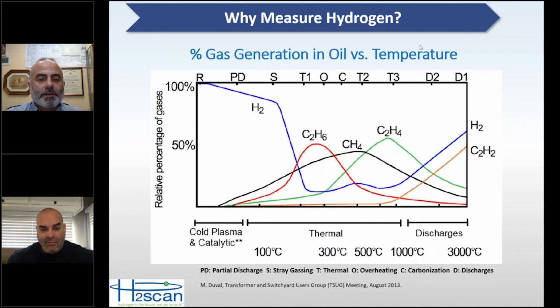And so this is an interesting graph that I came across at a conference a few years ago, and it really helped me make sense out of the different gases, when people would show me their DGA reports, of what was really going on. And if you look on a percentage basis at lower temperatures, and this is a relative thing, around 100, 150 degrees C, generally the primary gas you're going to see is hydrogen. And as the temperature increases, that's when you start seeing your methane, ethane, and ethylene increasing.